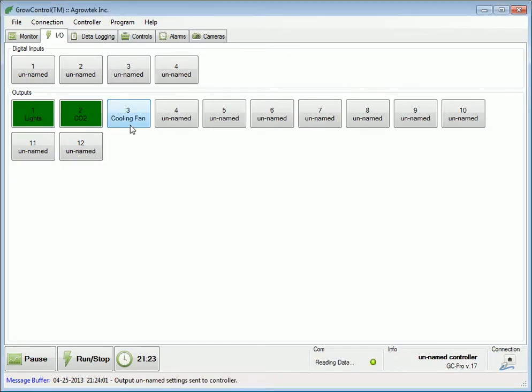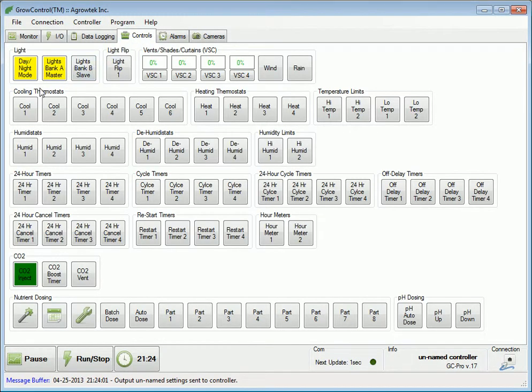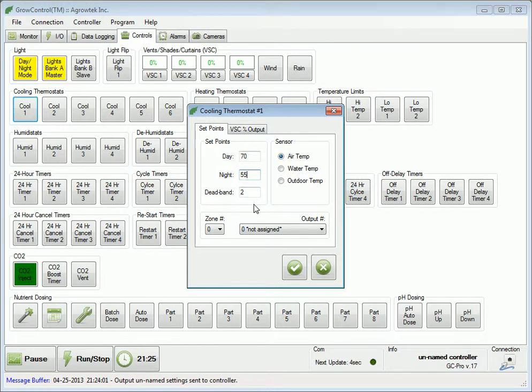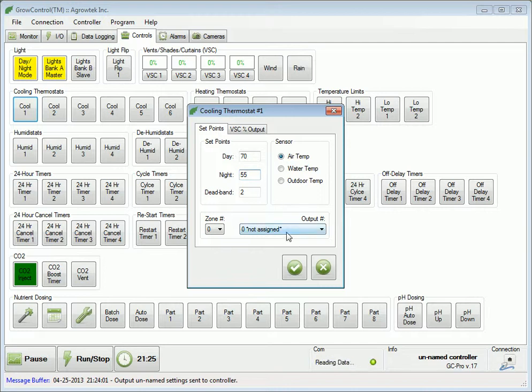Once we've set the output's name and settings, let's go to the Controls tab and pick a cooling thermostat. Some default values may already be entered — let's adjust them. The day and night set points represent the maximum temperatures we want in our environment. If the temperature exceeds these values during the day or night periods, the controller will activate the output. Let's select the cooling fan output that we previously labeled as number 3.